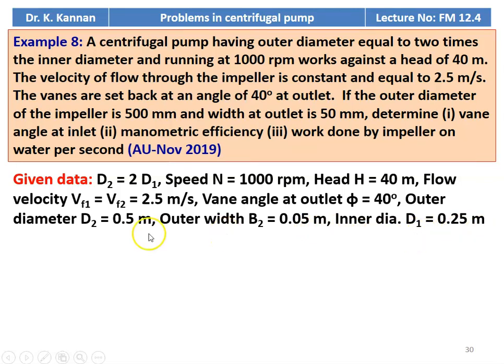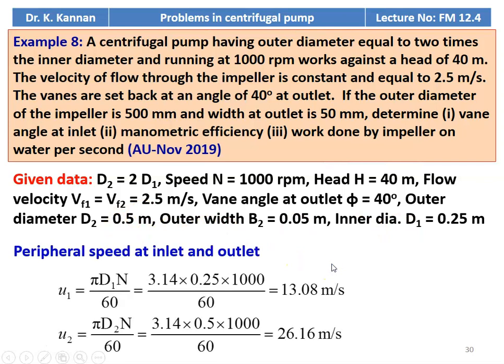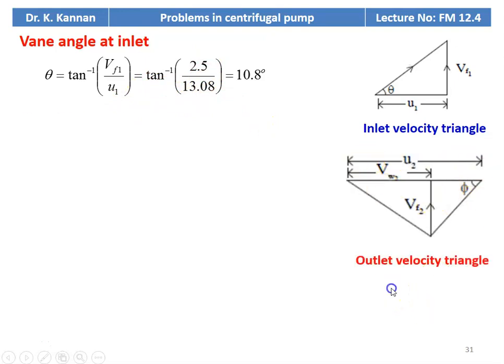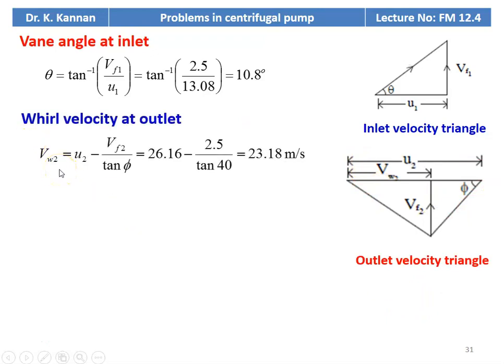Peripheral speed at the inlet: U1 equal to pi D1 N divided by 60: 3.14 into 0.25 into 1000 divided by 60 equal to 13.08 meters per second. U2 equal to pi D2 N divided by 60: 3.14 into 0.5 into 1000 divided by 60 equal to 26.16 meters per second. From the inlet velocity triangle, theta equal to tan inverse of VF1 by U1: tan inverse of 2.5 divided by 13.08 equal to 10.8 degrees. From the outlet velocity triangle, VW2 equal to U2 minus VF2 by tan phi: 26.16 minus 2.5 divided by tan 40 equal to 23.18 meters per second.